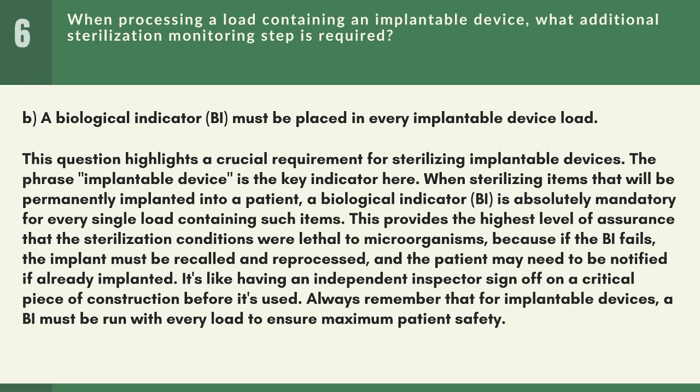Answer: B. A biological indicator, BI, must be placed in every implantable device load. This question highlights a crucial requirement for sterilizing implantable devices. The phrase implantable device is the key indicator here. When sterilizing items that will be permanently implanted into a patient, a biological indicator, BI, is absolutely mandatory for every single load containing such items.